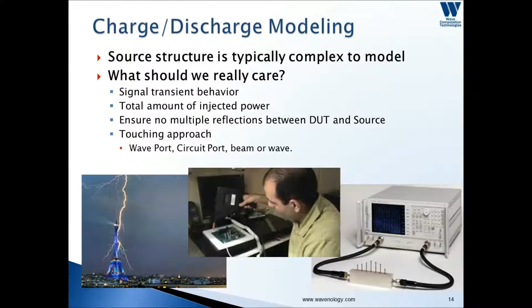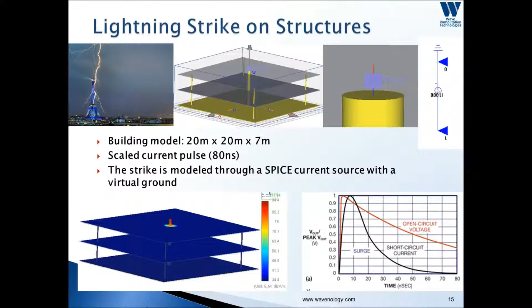Let's take a look at this example of which a lightning strike is hitting onto a 20 meter by 20 meter by 7 meter building. It is obvious that there is no need to model the cloud and the sky, but the touching point and the total amount of current being injected into the building matters. Here we use an equivalent circuit current source to represent the lightning strike current, and link such circuit port as a source in the 3D EM field simulation. The transient signals we used is a typical lightning strike signal from the IEC standard.